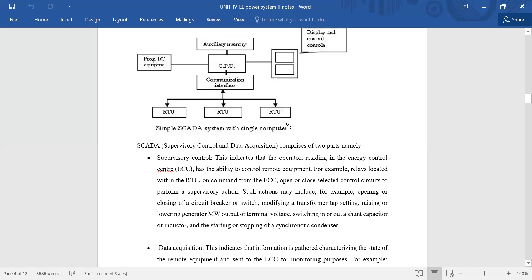For example, if we take a relay that is located with the RTU, remote terminal unit, on the command of the ECC, the Energy Control Center, it will open and close the selected control circuit, and it will perform a supervisory action. Such actions may include opening or closing of a circuit breaker, switching, modifying the transformer tap setting, raising or lowering the generator megawatt output or the terminal voltage, switching in or out of a shunt capacitor or inductor, and the starting or stopping of synchronous machines. Then we have data acquisition.